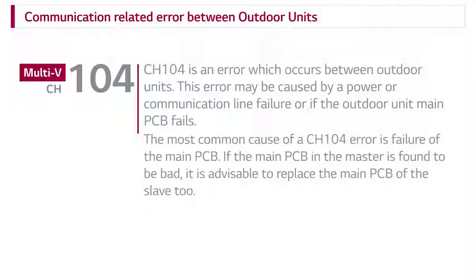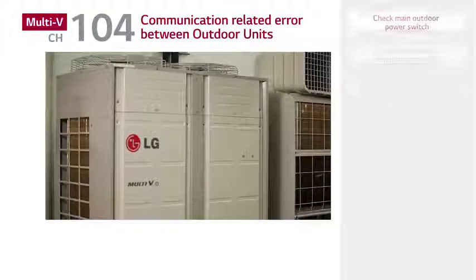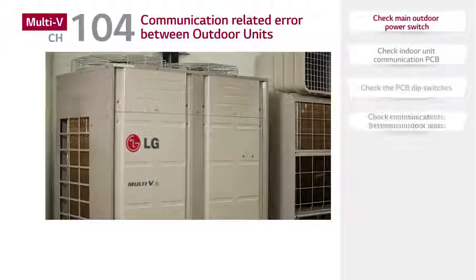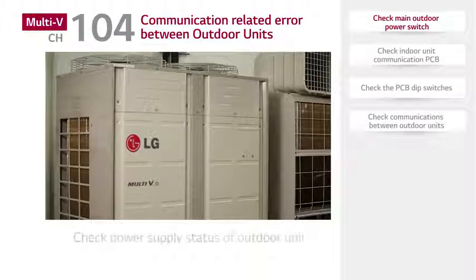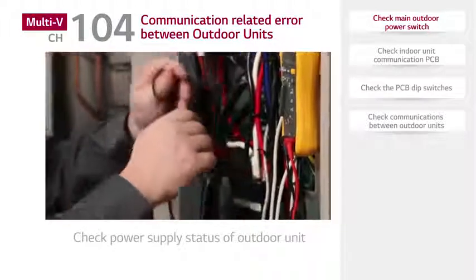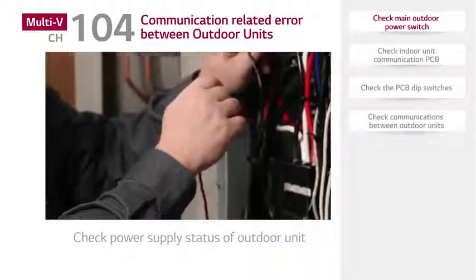If the main PCB in the master is found to be bad, it is advisable to replace the main PCB of the slave too. Check for proper power supply to the outdoor unit.